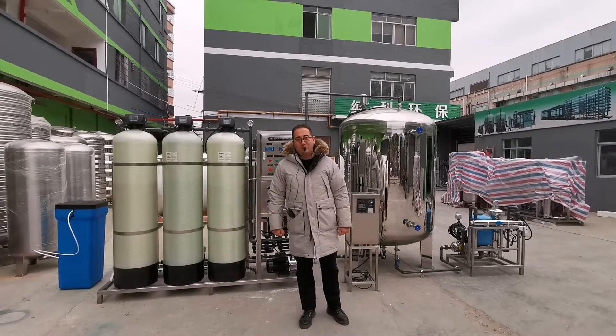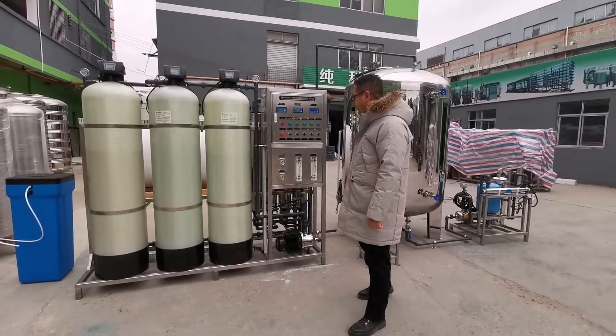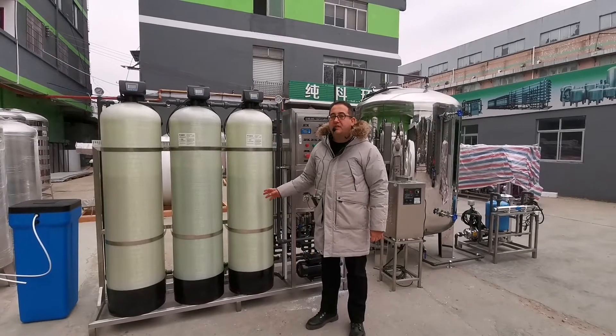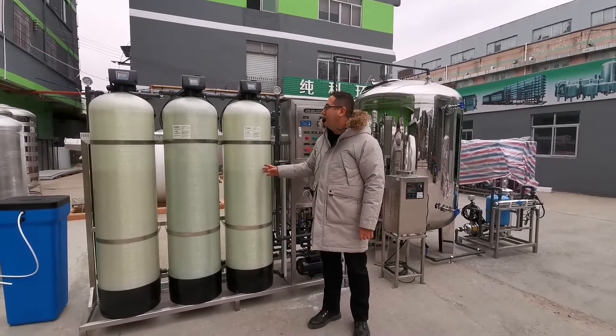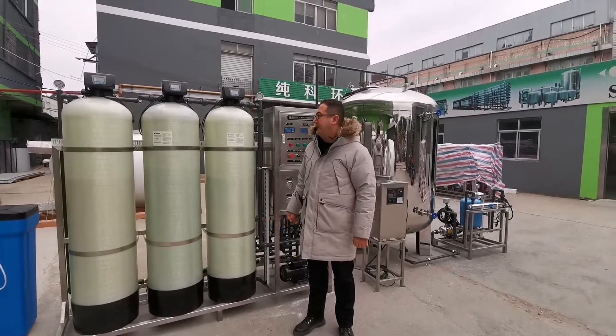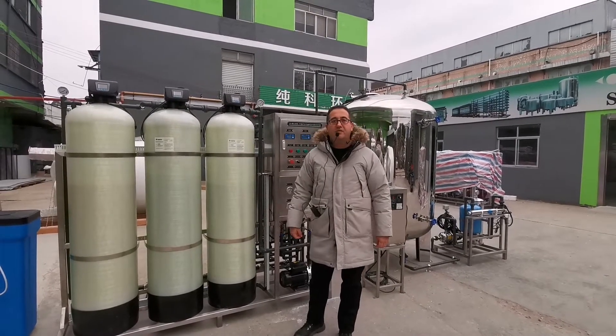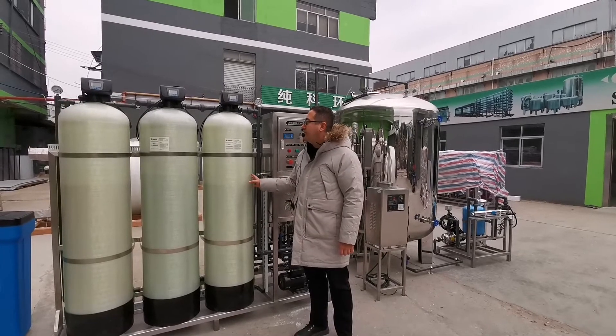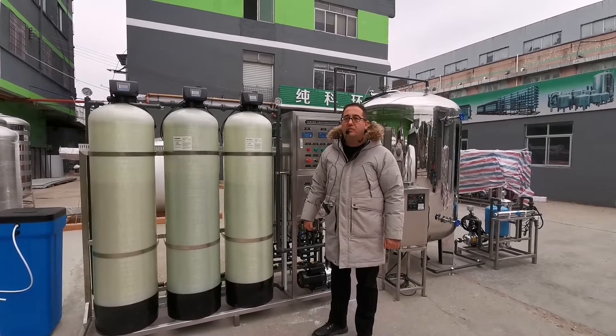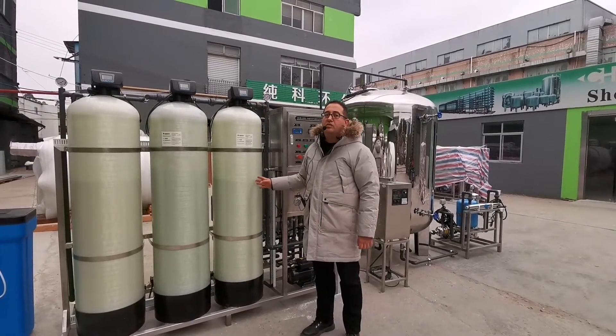The system starts from the raw water pump. In this project we use a CNP brand water pump. After the water pump, we have three pre-treatment filter tanks. These FRP tanks are 500 mm diameter and the active height is 1750 mm. The system is automatic and we use Runxin automatic valves. The water comes first to the sand filter.